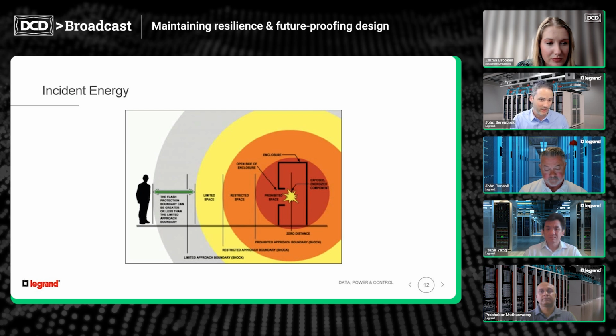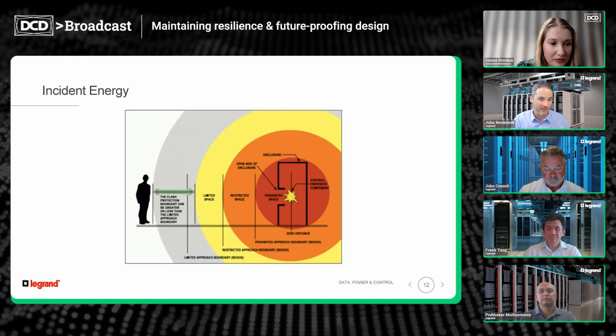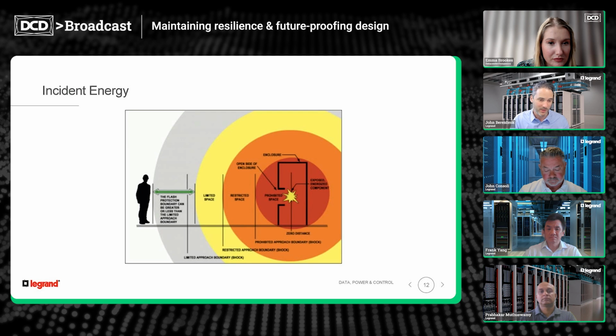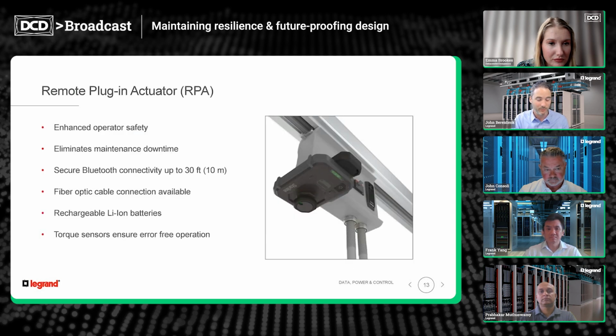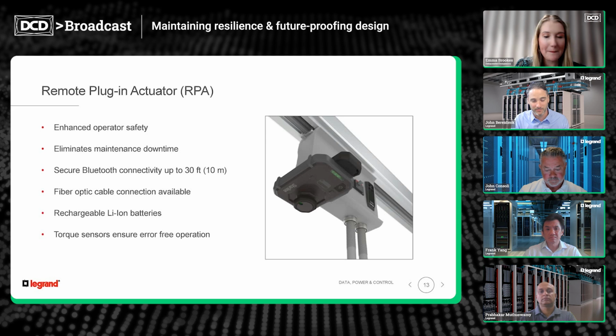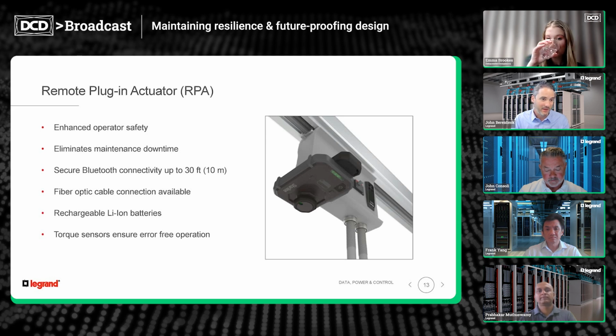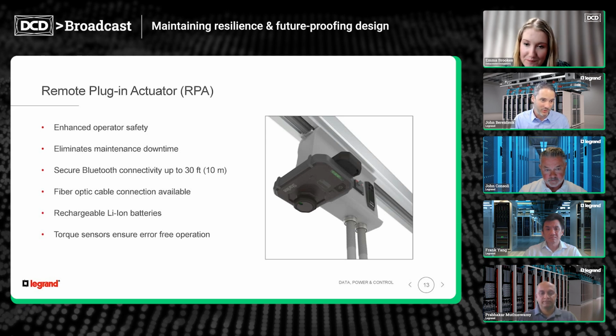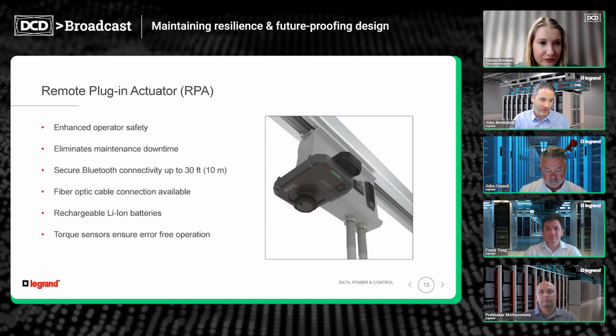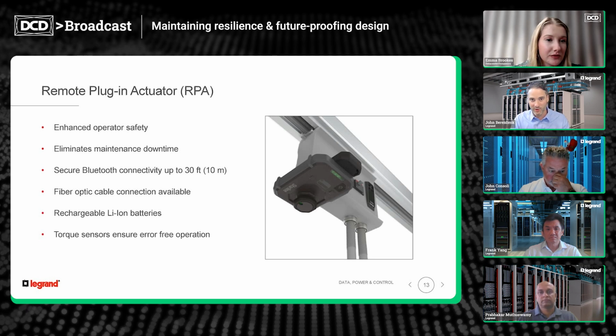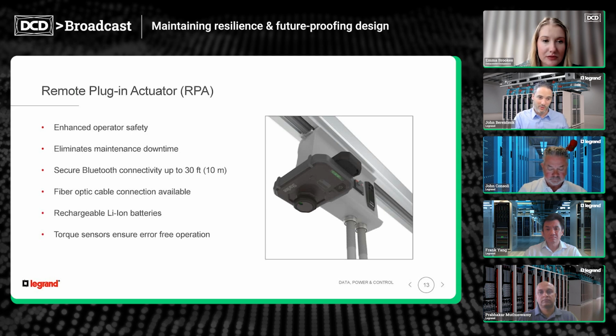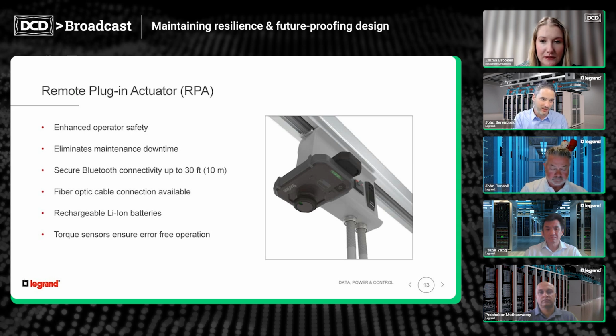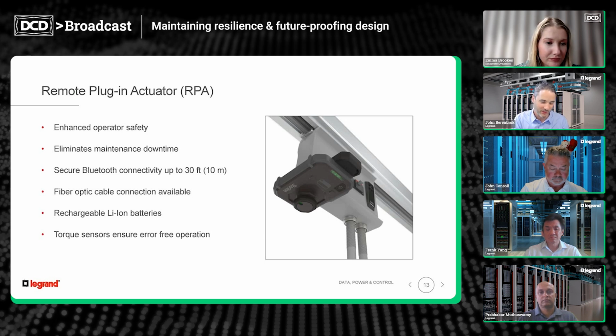Another example is adding flexibility back into the system by avoiding maintenance shutdowns, using what we call an RPA, our remote electrical engagement tool. That enhances operator safety by allowing the operator installing our plug-in unit to do it live without taking down the system. They can step outside the arc flash zone, use the remote control, engage the plug-in unit into the busway, come back, remove the tool, flip on the breakers, and they're good to go. It's a multi-pronged approach.